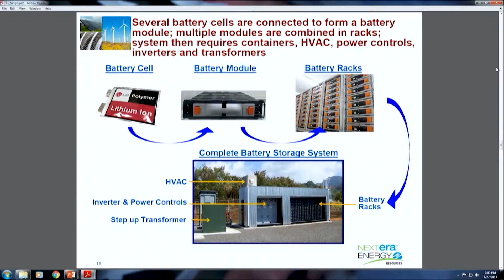Now the battery in itself is not good enough - you still need a system and architecture around it. You need to rack it up. The smallest denominator is a cell. You have seen cells - let me go to the next picture. On the left, you'll see a pouch cell. Manufacturers make different shapes and sizes - they could be cylindrical cells that you see in Home Depot and Lowe's, typical AAA and AA batteries. You could have prismatic cells. These cells then need to be scaled up, so they typically put them in a module, and then rack up all those modules. They're like file servers - you rack them all up, and at the top of the shelf is usually a BMS, what we call a battery management system. It's like the brain of the whole rack.